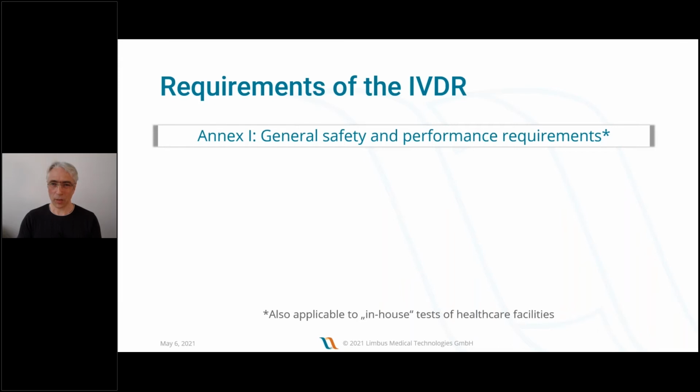If we now take a closer look at the requirements, where the bar has risen a lot for software, there is, of course, Annex 1 that states the general requirements for IVDR products. And as Sebastian already mentioned, these general requirements apply to all medical devices, all IVDs, no matter if they are used in-house as laboratory developed tests, or if they are properly marketed medical devices.